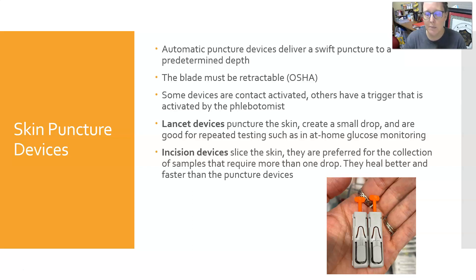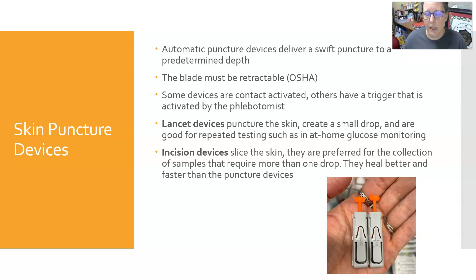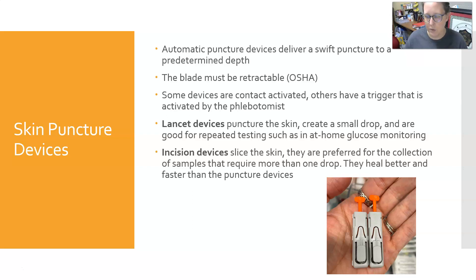Some devices are contact-activated, meaning they activate when pressed against the skin, while others have a trigger the phlebotomist must press to activate. Lancet devices puncture the skin creating a small hole, tend to produce smaller drops, and are good for repeated testing such as at-home glucose monitoring. Incision devices slice the skin, are preferred when more than one drop is needed, and heal better and faster than punctures.